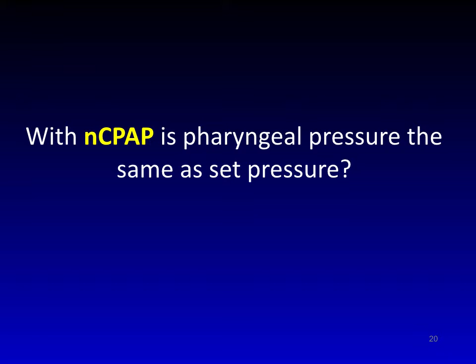So Tony DePaoli did his thesis on looking at pharyngeal pressures in babies on CPAP. And this is bubbly bottle CPAP. That's why the CPAP pressure is the red line, and it's bubbling as the water bubbles out of the bubbly bottle. The air bubbles out of the bubbly bottle device. And we've got 2 pharyngeal pressures being measured, just in case one wasn't working very well. And what you see here, if you look at the beginning and the middle section with the mouth open, although it says it's giving a pressure of 7, the pressure in the pharynx is only 3.